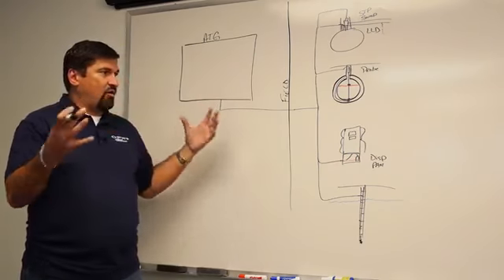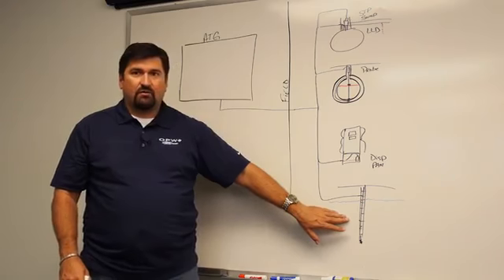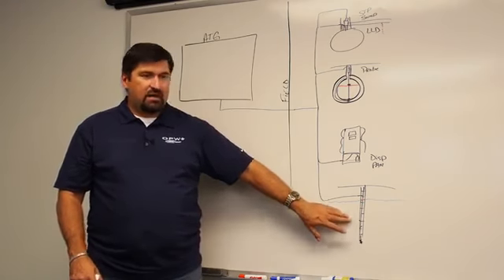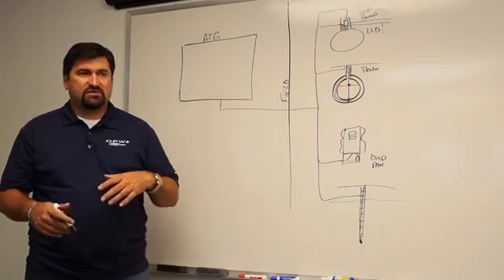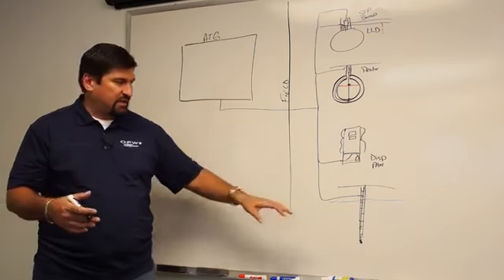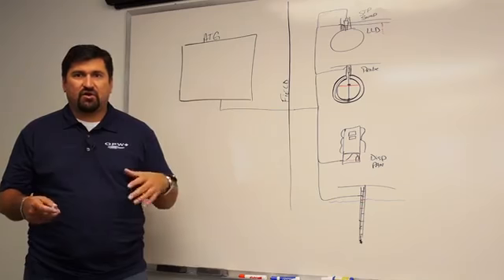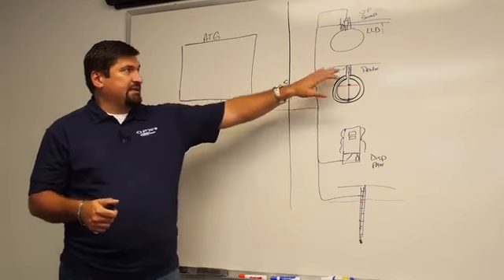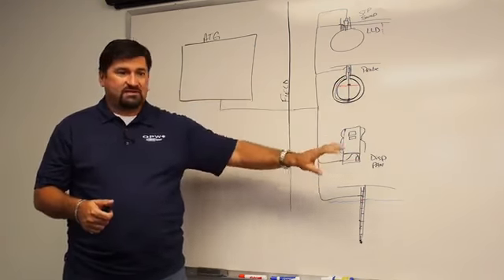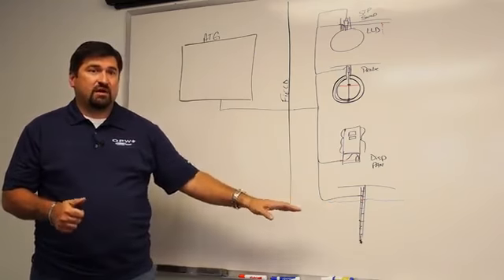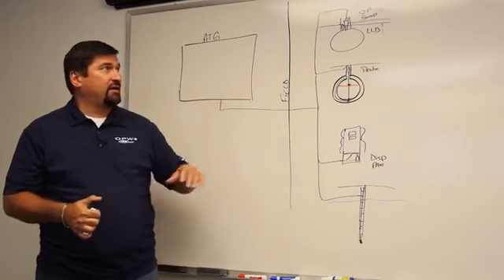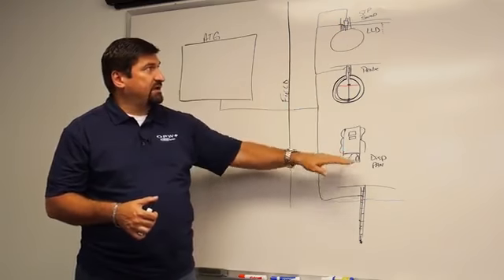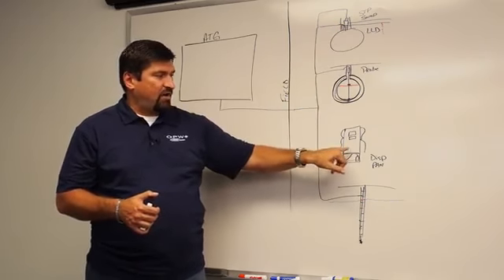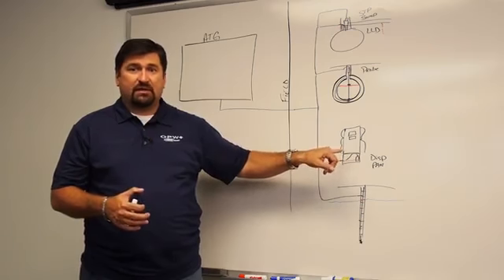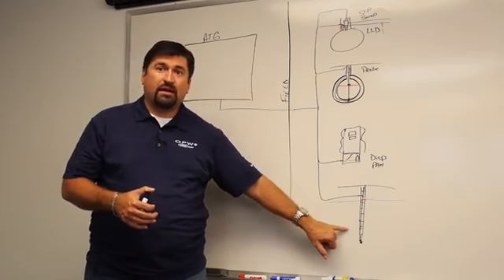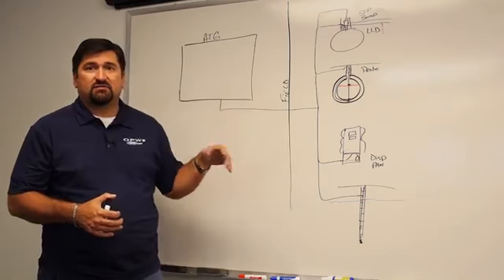Well, when you take that and go out even further, you're looking at the monitoring wells around the exterior of the site. These are put down to make sure that, it's almost like big brother's watching. The monitoring wells let you know if there's any breach inside a tank that may not be picked up by a probe or a sensor, or may be coming from some other source outside the leak detection area. Underneath the dispenser and the STP, there are places outside the leak detection capability of the gauge that the monitoring well would pick up that your leak detection system may not.